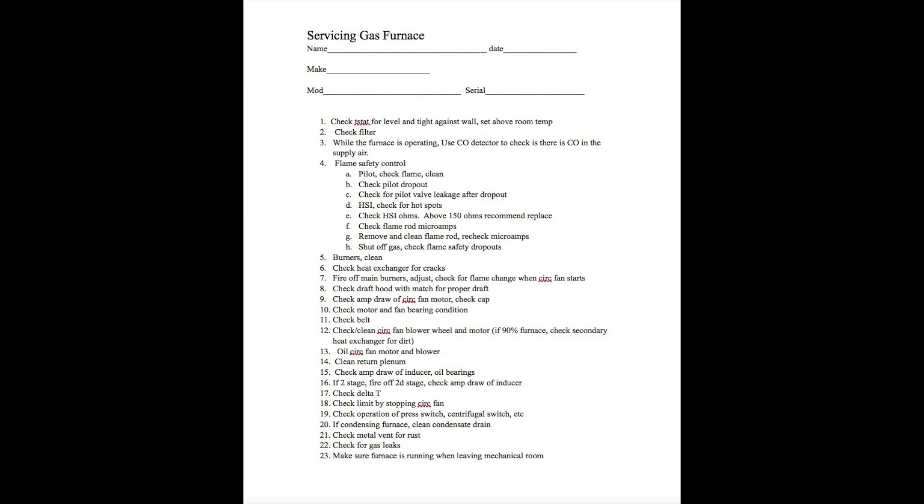Check and clean the fan blower and motor. That circulating fan can get a lot of dirt in it in a short time if someone has neglected to change filters or doesn't put a filter in it at all. You got to look at those fan blades, determine whether it's ready to be cleaned or it's okay. To clean it, you're going to have to pull the blower assembly out and wash it. Now, if it's a 90% furnace, you may want to pull that blower out and check the secondary heat exchanger. If for any reason you take a 90% furnace and pull the blower out, you want to go under there and check that secondary heat exchanger. It looks like kind of an air conditioning coil and it can get pretty plugged up.